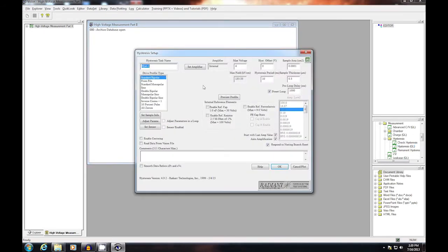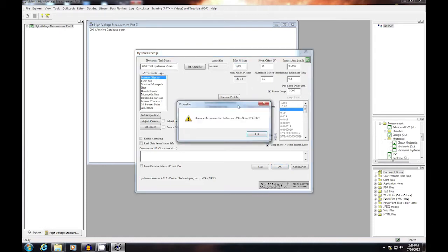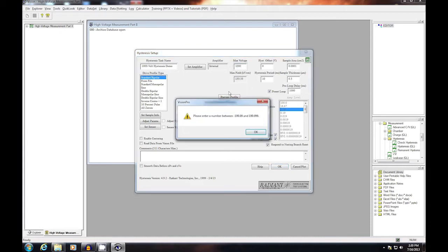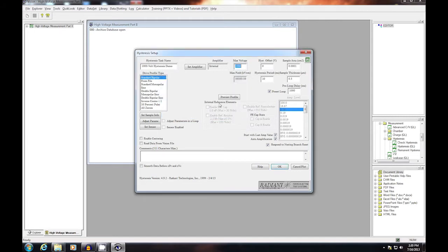Start by giving it an appropriate and unique test name. Then I'm going to assign a thousand volts. And when I do this, you'll find that you're going to see an error. The reason the error appears is that the external high voltage amplifier is not enabled in software. So what I need to do is acknowledge the error and reset a lower voltage.